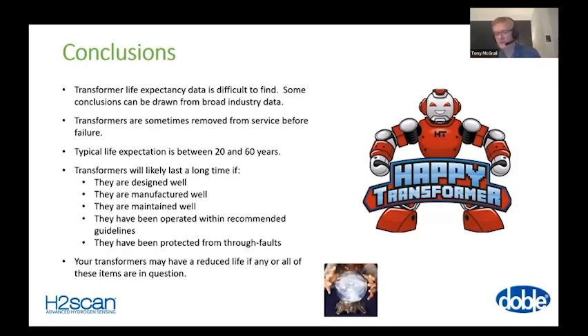Well, let's look at the rest of the population. For each of those, we need to treat them as an individual. For each transformer in our population of interest, we have to collect data, analyze the data, and then see whether there's any failure mode in operation, and consequently how much life has been lost from the capability of the transformer.